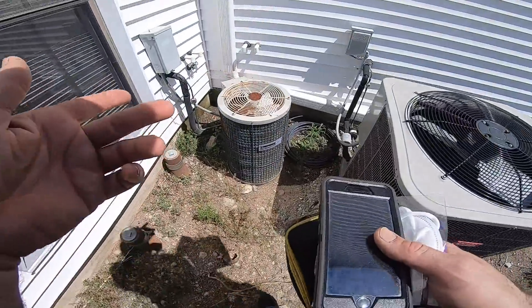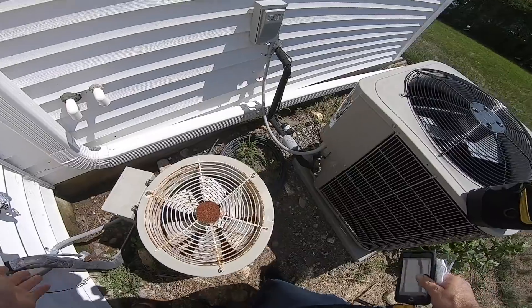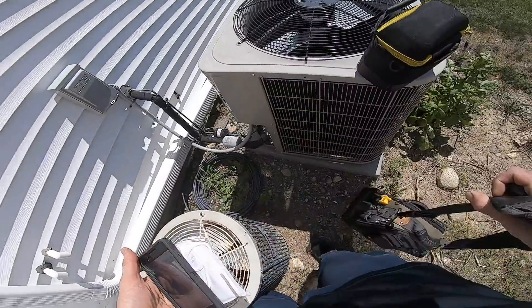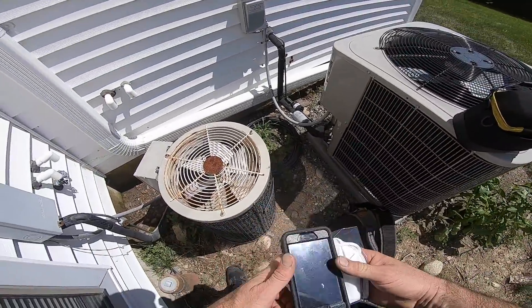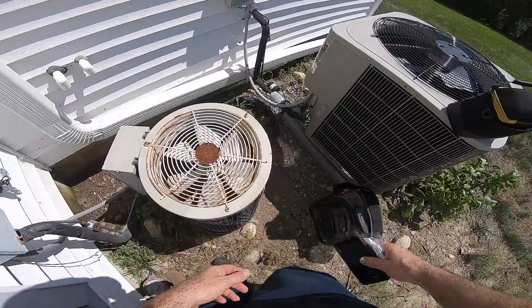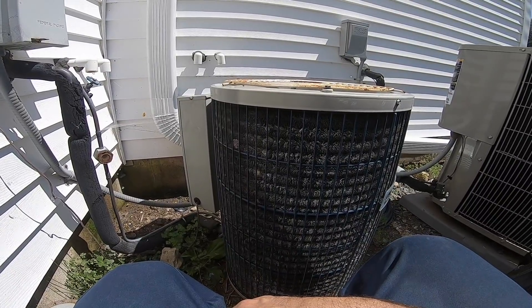Here's the unit - water running out the drain, a lot of water. Wondering if it's frozen; this has been off for a while supposedly. Let's see what happens when it starts, because it's bothering me that that much water is still coming out when it was blowing warm. Tiny little fan, nice old unit. Still leaking quite a bit of water - that's making me believe it's frozen.